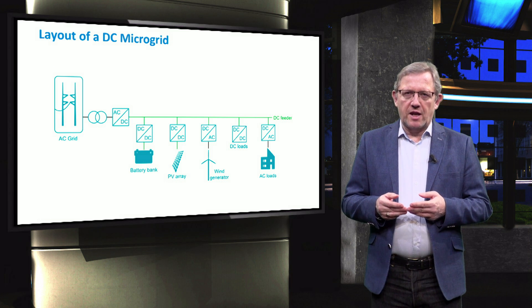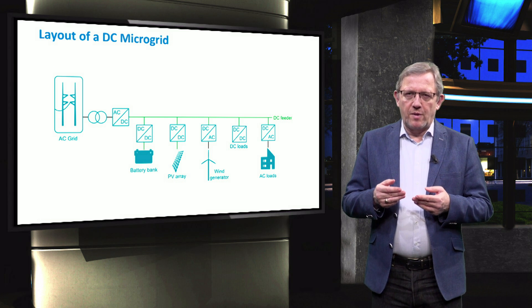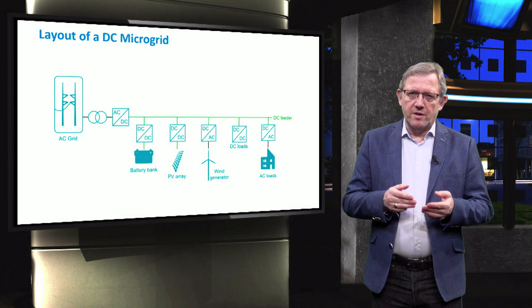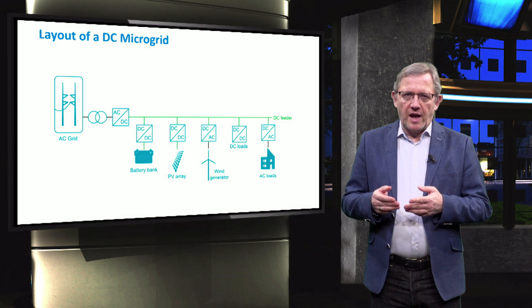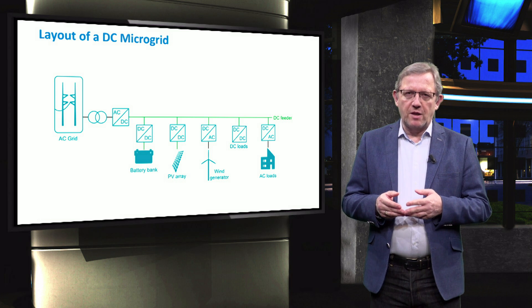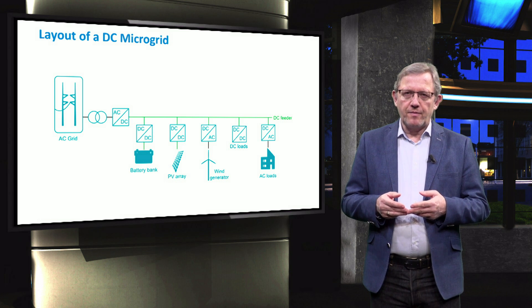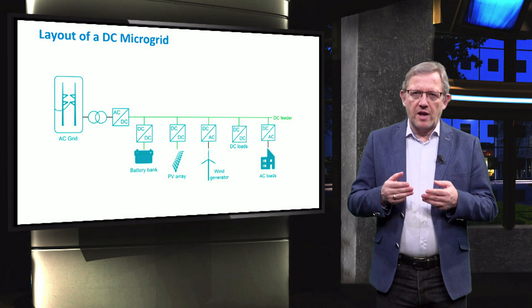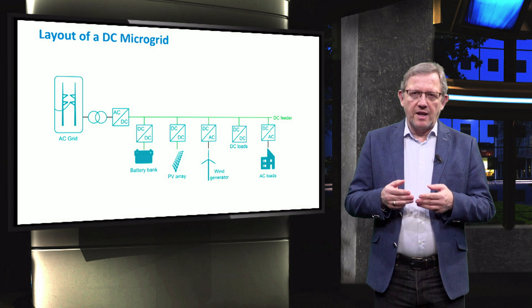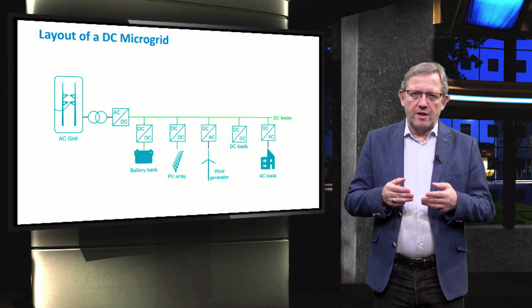The DC microgrid architecture presents some advantages over the AC microgrid: a reduced number of power converters and more simple DC-DC and DC-AC rectifiers, the possibility to adapt the DC bus voltage to the microgrid requirements, and a very high quality of the DC bus voltage, allowing some DC loads to be connected directly. The main drawback is the series-connected bidirectional AC-to-DC converter handling the whole power flow from and to the distribution grid, reducing its reliability.